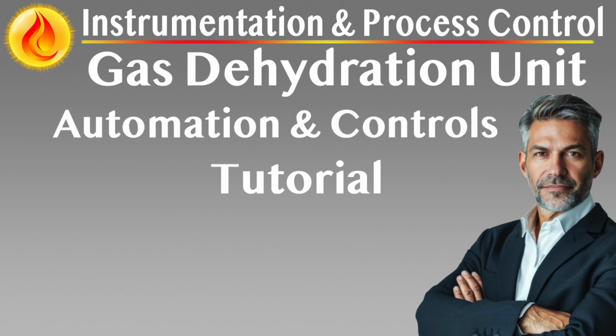Bottom section glycol level control. A dedicated level controller, LIC, and associated level control valve, LCV, maintain normal rich glycol level before forwarding to the flash vessel. Level high trip, LSH, protects against column flooding, while low trip, LSL, alerts to potential vapor breakthrough or glycol starvation.